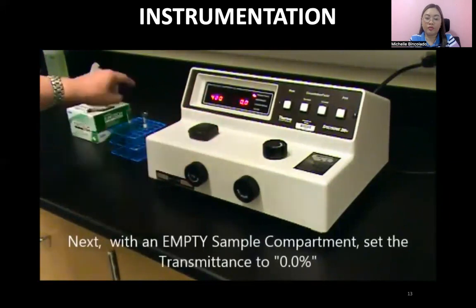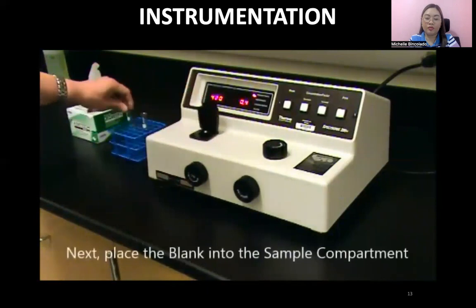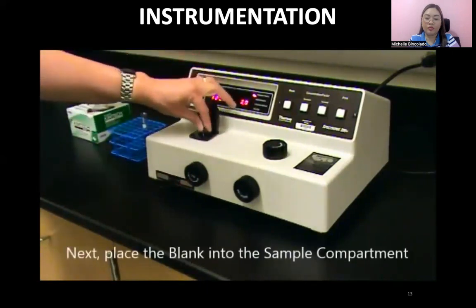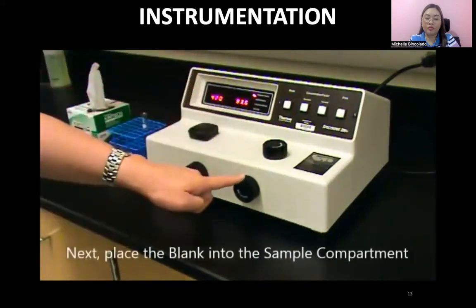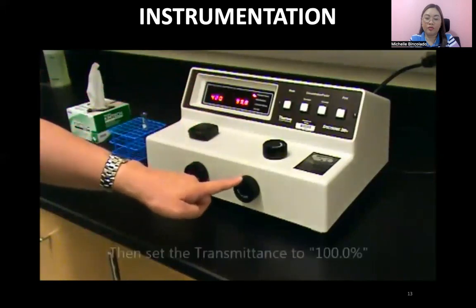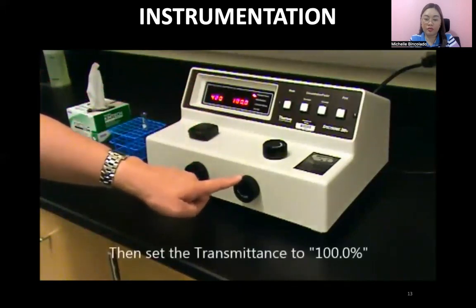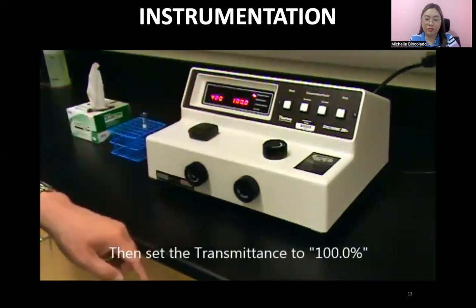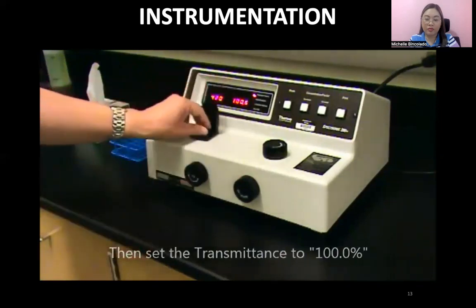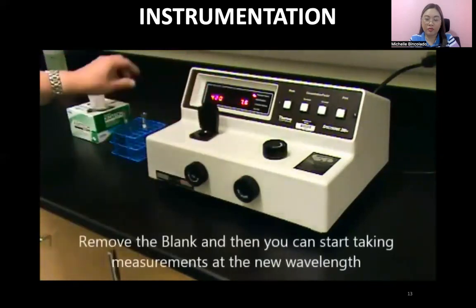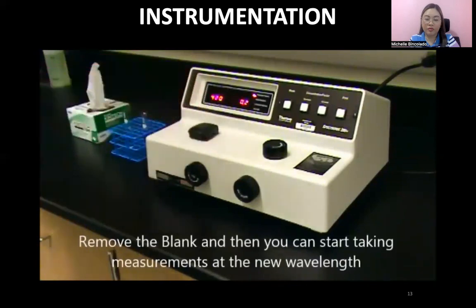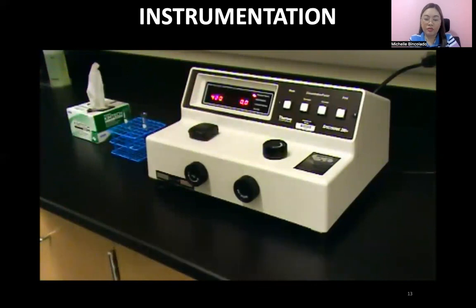Then we'll have to put the blank cuvette back in. And then we'll have to use the knob on the right, the absorbance transmittance control, in order to set the machine back at 100% transmittance. And then after that's complete, you can go ahead and put your sample in to read the absorbance or transmittance at the new wavelength.